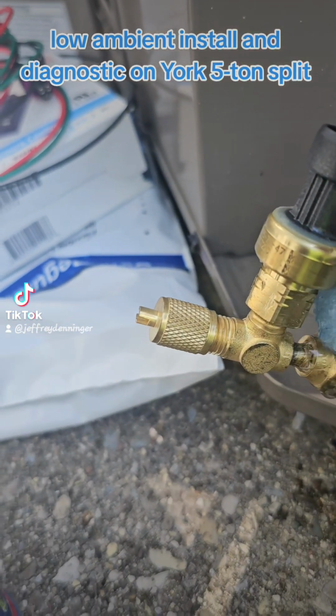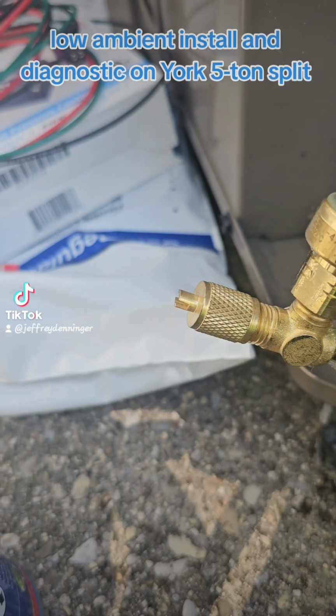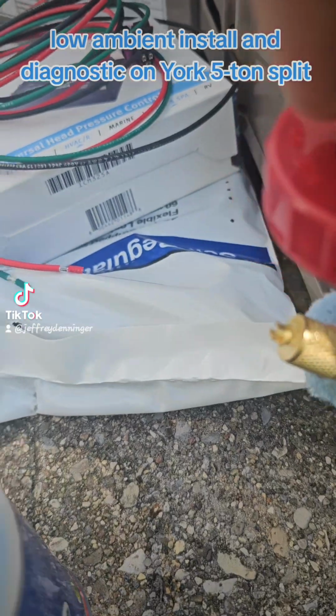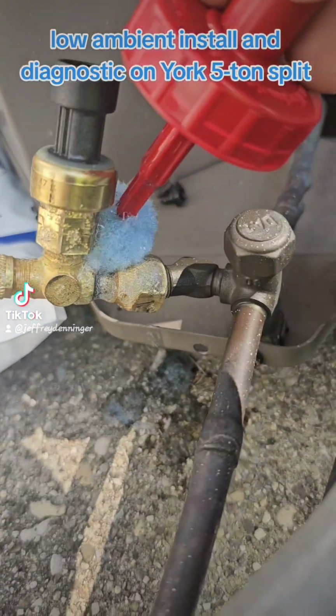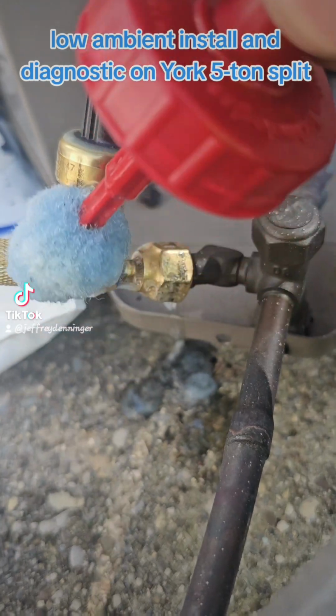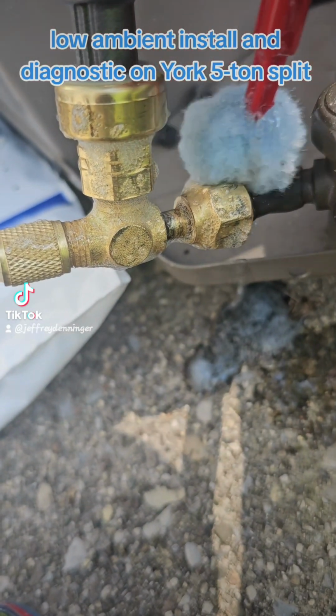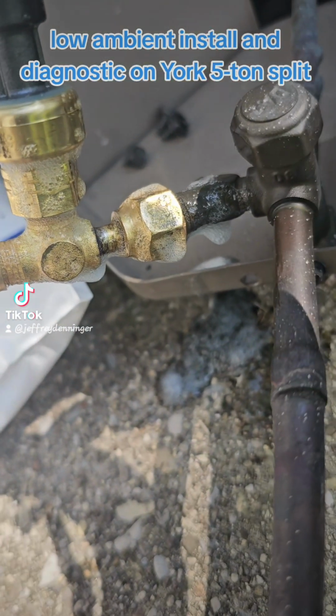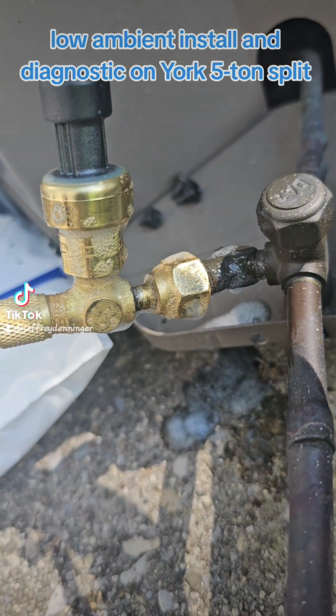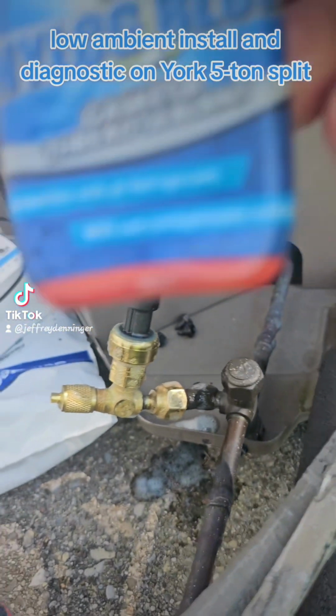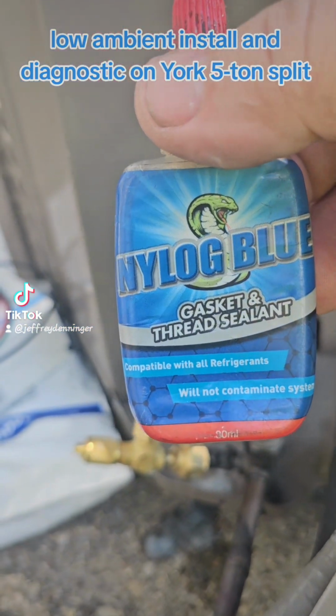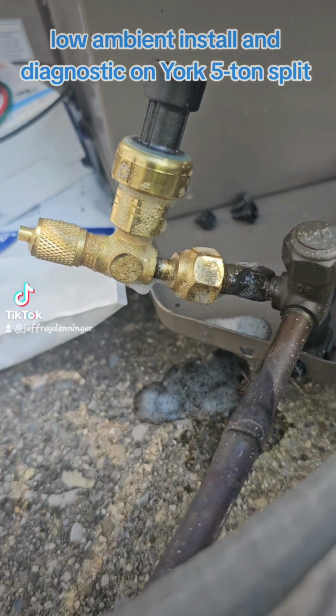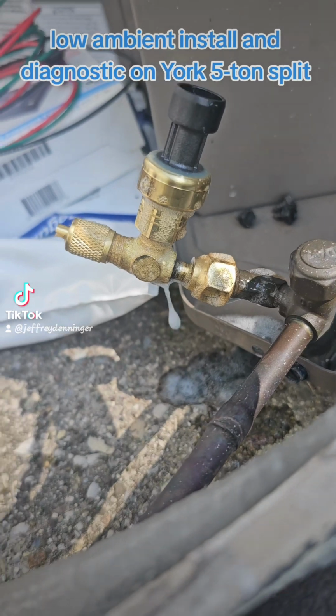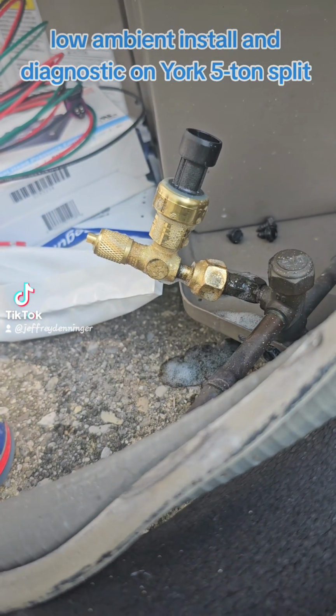Now we're going to check for leaks. Make sure we don't have any leaks here. And the system is live. No leaks. Everything was installed with Nylog Blue. Time to start installing some of the rest.